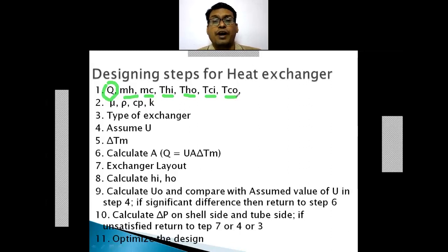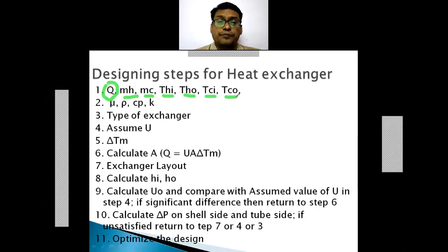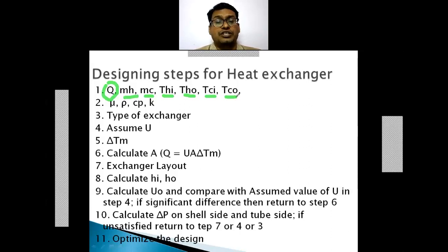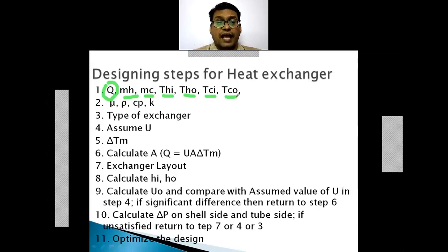Next is to select the type of heat exchanger — whether it is a shell and tube exchanger, a plate type heat exchanger, or a spiral type heat exchanger. With a little modification we can change this designing procedure, but the basic steps are the same. Then, assume the overall heat transfer coefficient U, based on specific numerical values provided in the literature by different authors, drawing on the past experience of different people.